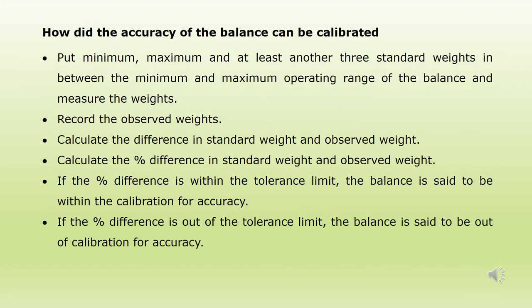How can the accuracy of a balance be calibrated? Accuracy calibration is performed by weighing minimum two standard weights representing the minimum and maximum of the balance operational range. For example, if the balance capacity is 1 kg and the operating range is 1 gram to 1 kg, the balance should be calibrated using 1 gram and 1 kg known weights for accuracy. The observed weights are compared to the standard weights and the percentage difference is calculated. If the percentage difference is within the tolerance limit, the balance is said to be within calibration for accuracy.